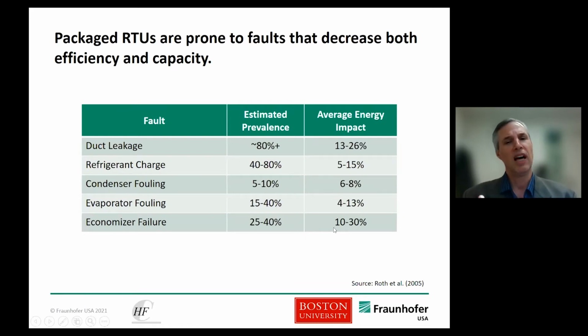This is something where a lot of buildings bring in cooler air when it's 55 degrees outside. They still need some cooling, so they'll bring in the cooler air to cool the space. But if this outdoor air damper is open at a larger setting than needed just to provide ventilation air, and it's doing that when it's hot and humid outside or when it's quite cold outside, you have suddenly increased your building loads, in some cases dramatically. That can have a significant impact, particularly if you have a very efficient building and the shell loads have gone way down, and now you've brought in a bunch more air that has to be conditioned. So these challenges exist for a large portion of these workhorse types of units and really compromise the real world effectiveness.